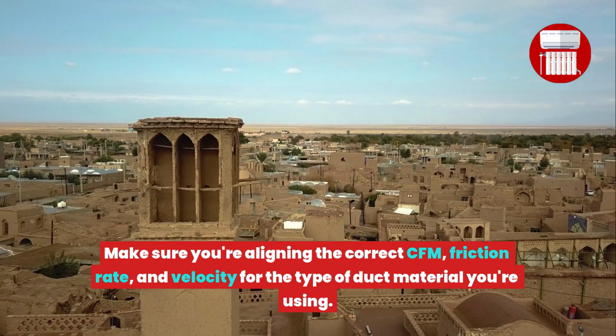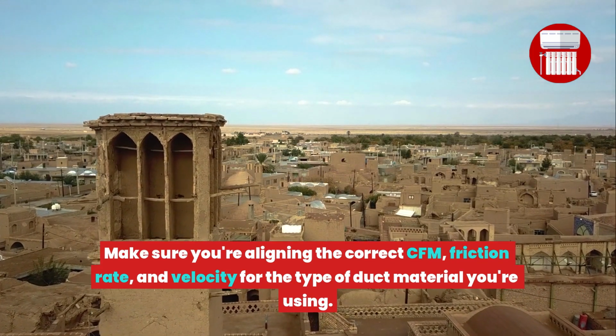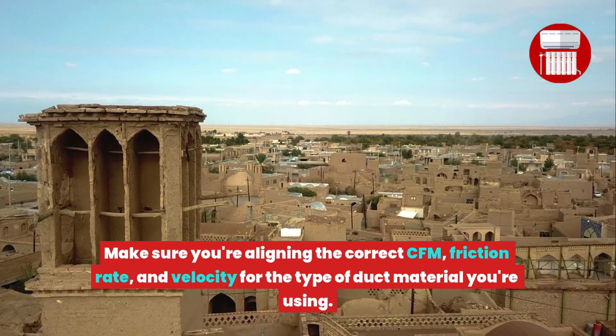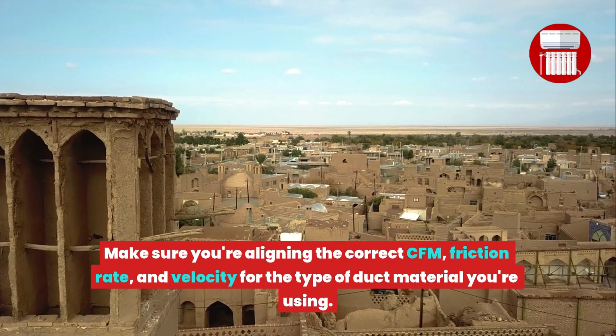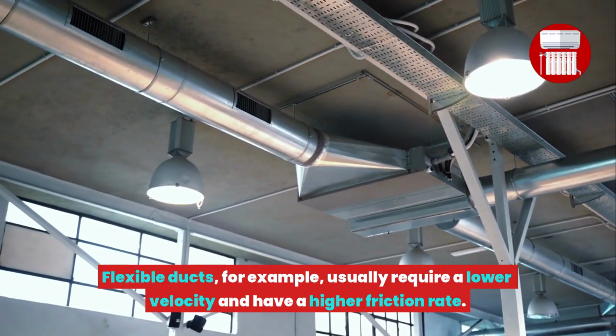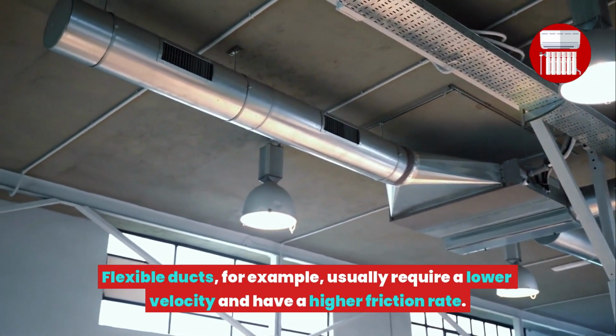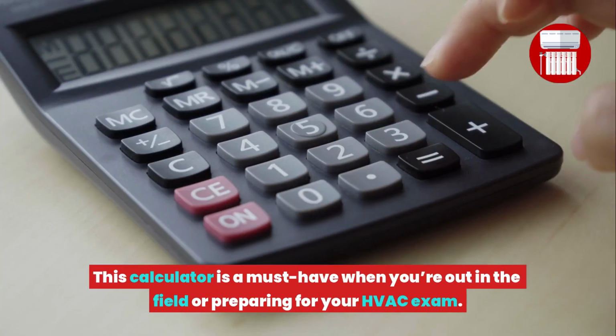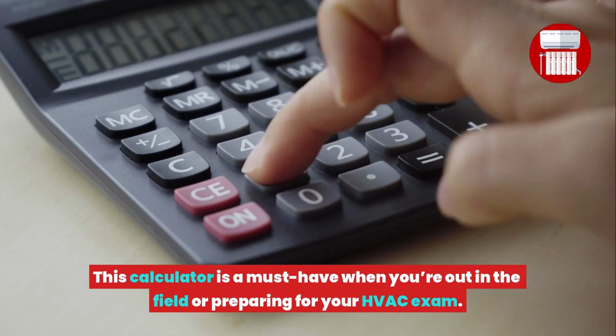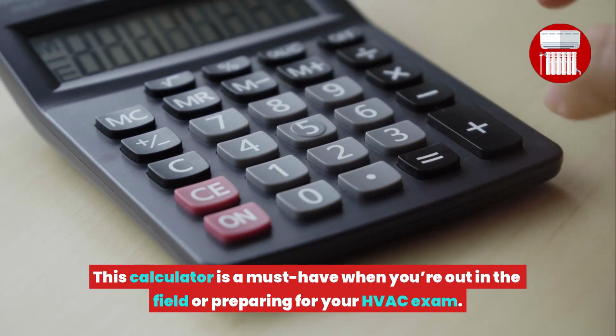Final tip: make sure you're aligning the correct CFM, friction rate, and velocity for the type of duct material you're using. Flexible ducts, for example, usually require a lower velocity and have a higher friction rate. This calculator is a must-have when you're out in the field or preparing for your HVAC exam.